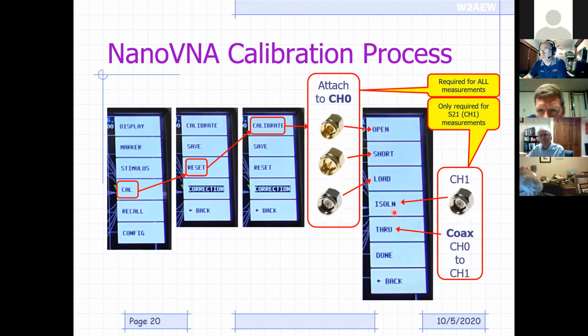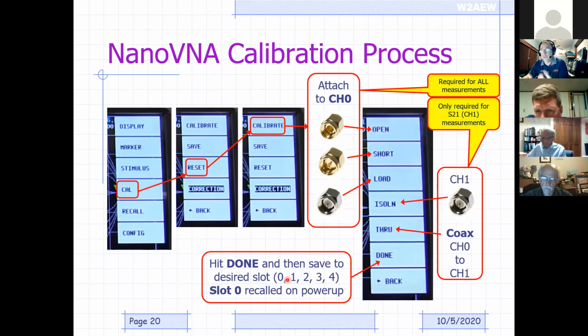The isolation measurement is either leaving the ports open, or you could attach a load to channel 1 to kind of isolate it even further. And then the through is connecting the ports together. So once you've done the first 3 or all 5, then you hit done. Okay, and then it'll prompt you for a memory slot. What memory slot do you want to load things into?